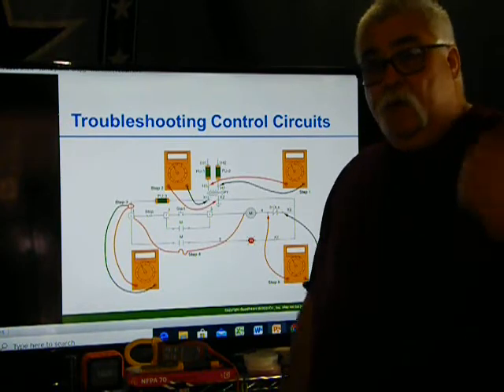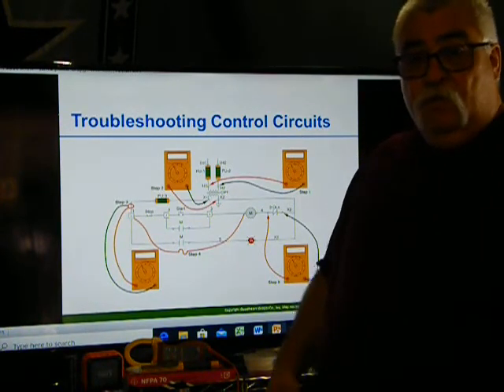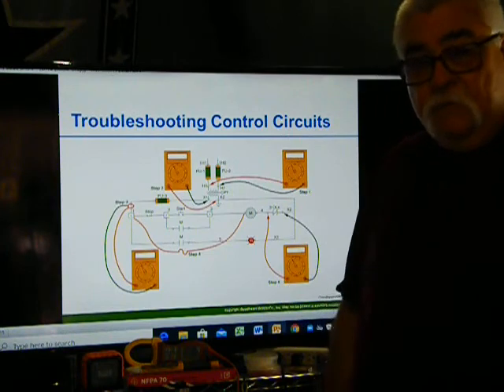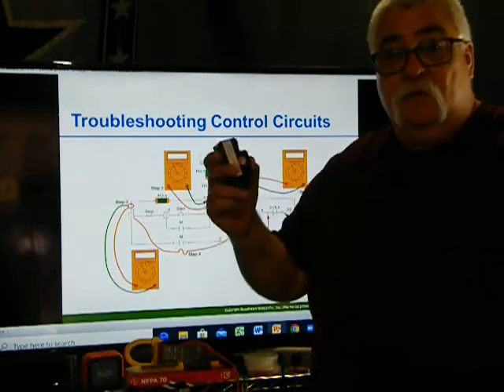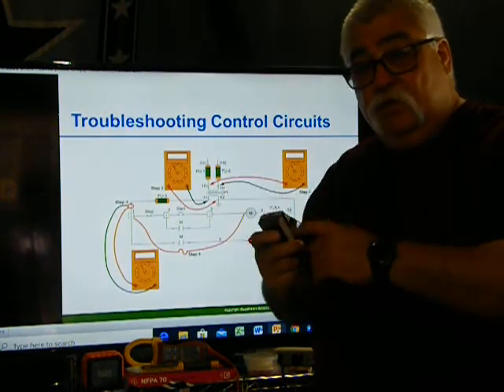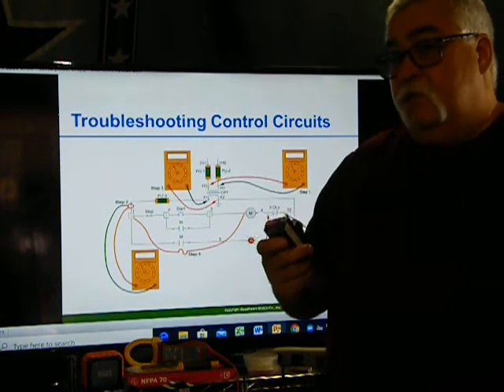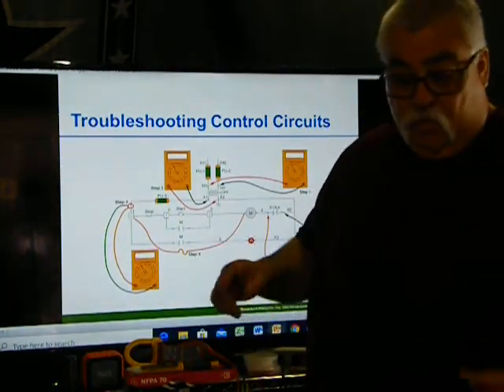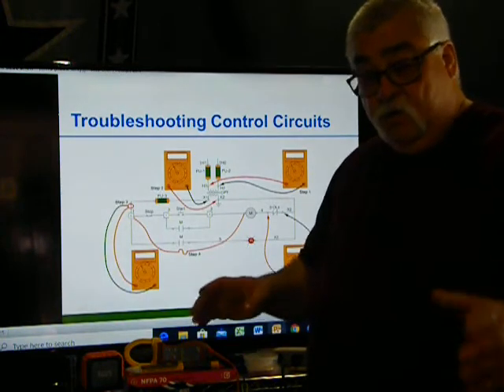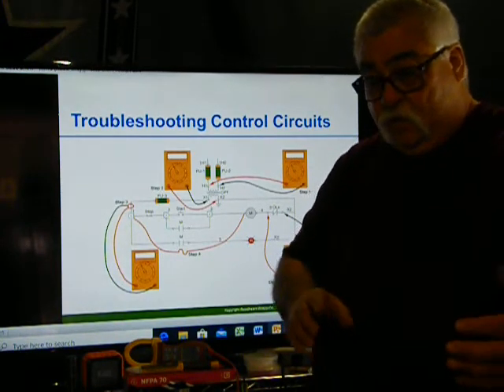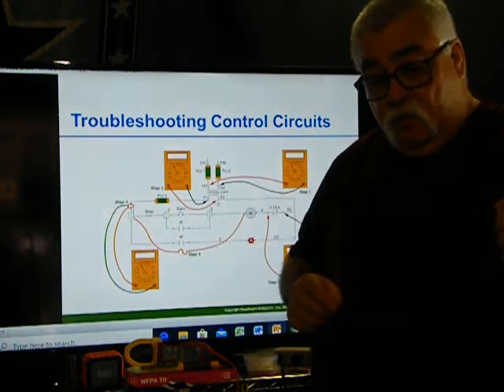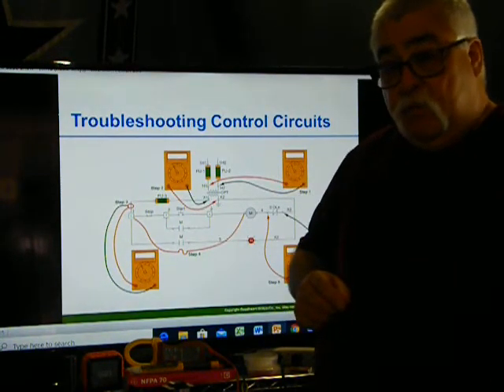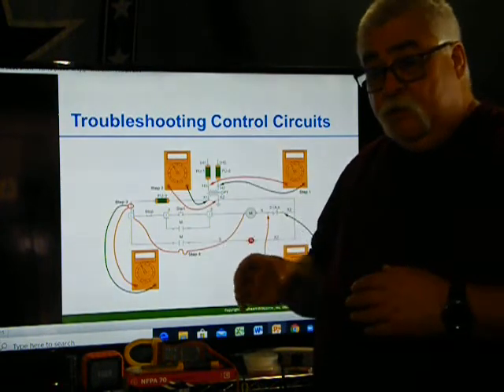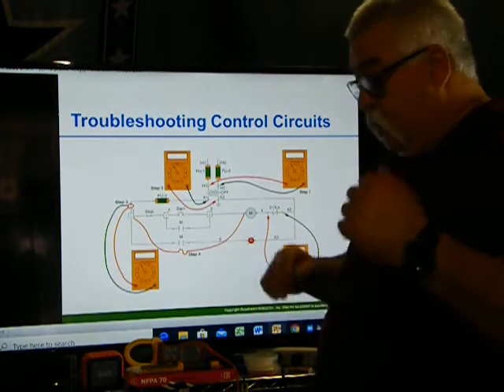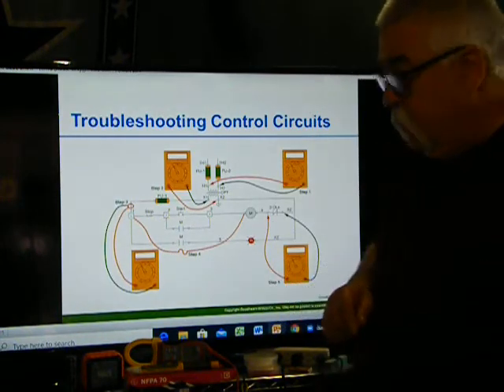And then he called me up, hey Mundo, we got a motor that doesn't stay on. We don't know what the problem is. We just changed it out. It's a brand new motor. Okay, what's causing it? The overloads. Why? Because the overloads were sized for the 5 horsepower, not sized for the 7.5. Okay, so it's one thing you should look at. You look at the motor, you try to make sure that you're looking at the motor, and instead of replacing what's there, you try to find the size of the overloads for that motor, and then you just change them out. Okay. The other thing is always check to make sure your motor is good.